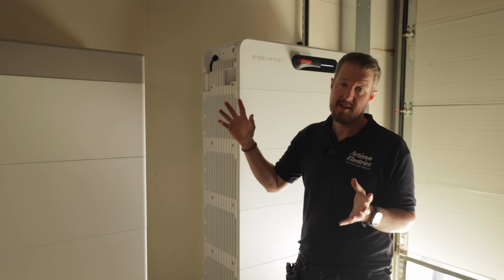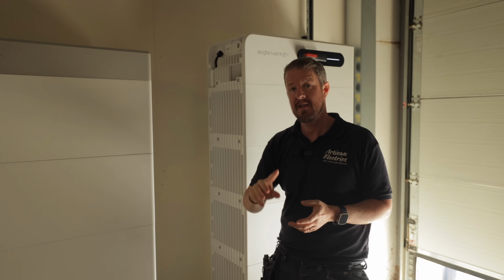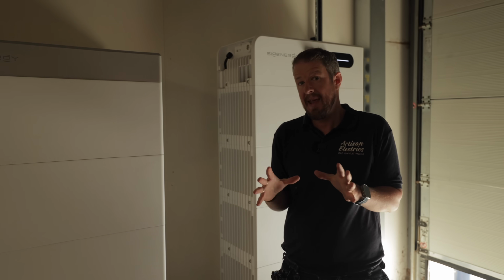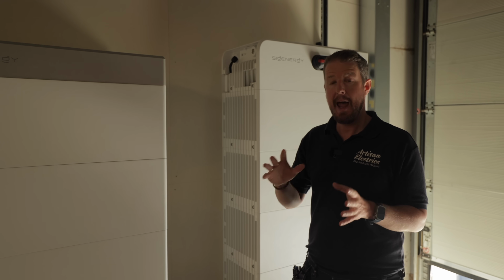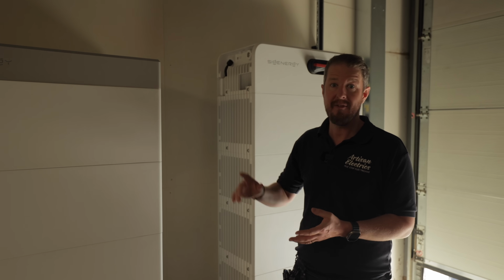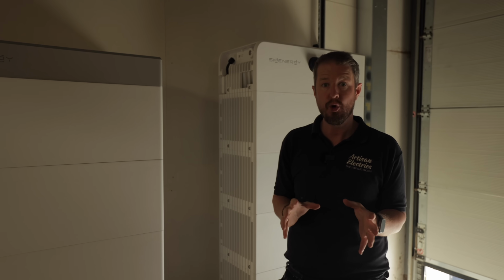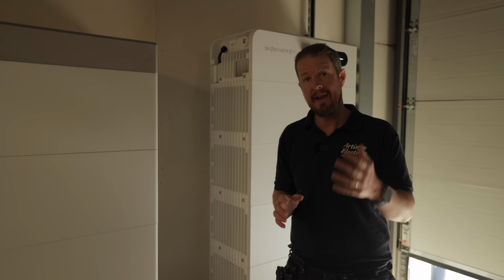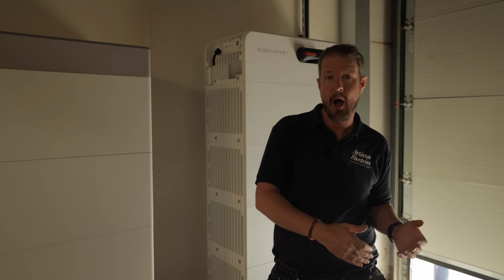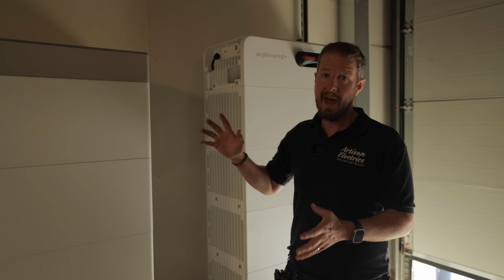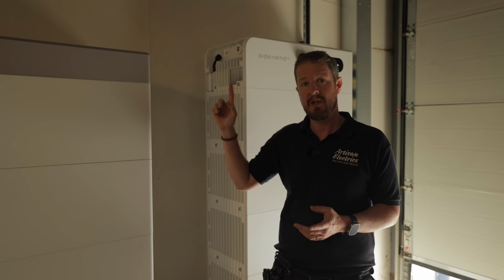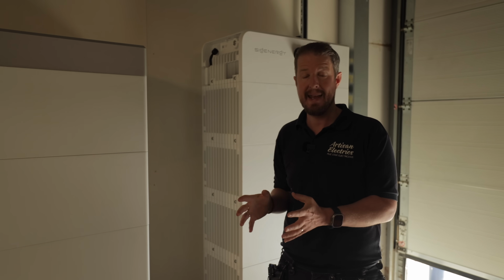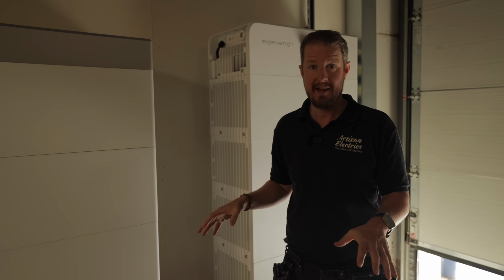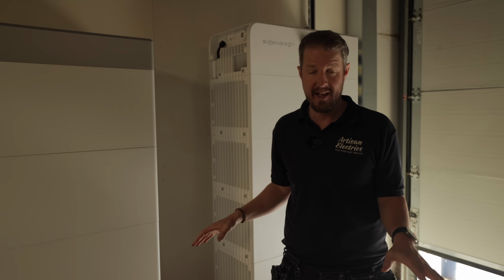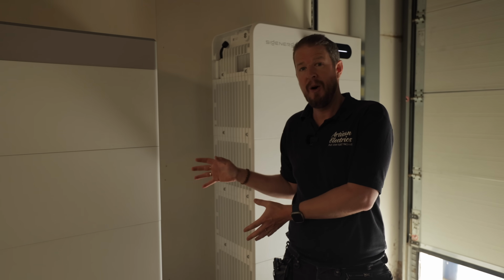Now, when it comes to the inverters, Sigenergy make 3 variants. There's the M1, which is purely a PV inverter. There's the M1HYA, which is a hybrid inverter like this, but designed for on-grid systems only. And you can connect PV to it only, you can connect battery only to it, or both. And then there's the inverter that we've selected for this project, which is the M1HYB. That is designed for on and off-grid scenarios. And in this case, it allows us to go completely off-grid if we want to, with backup power from these batteries.